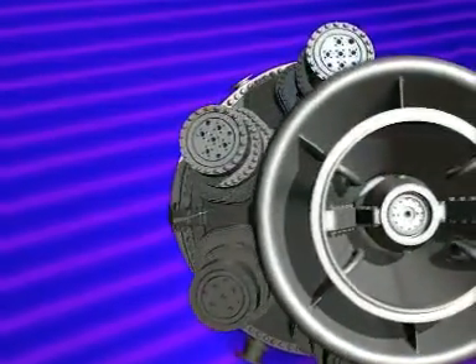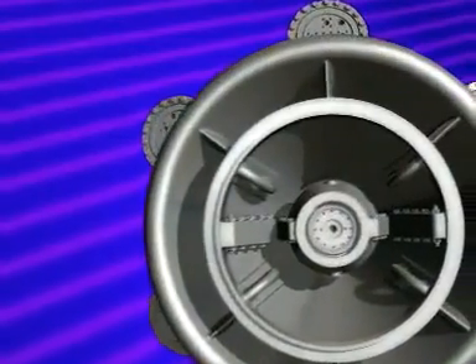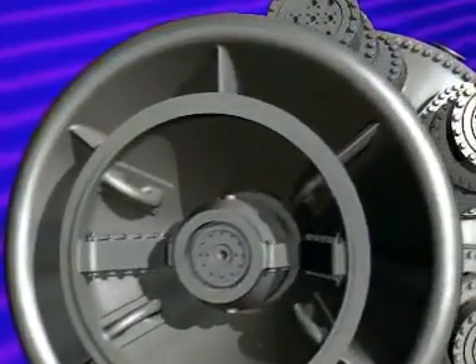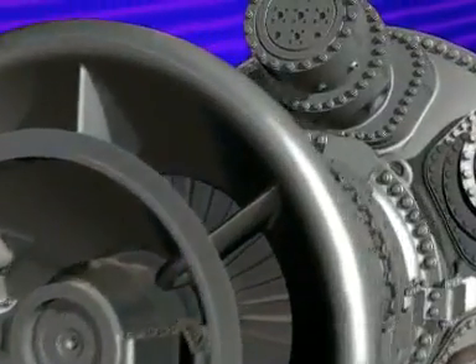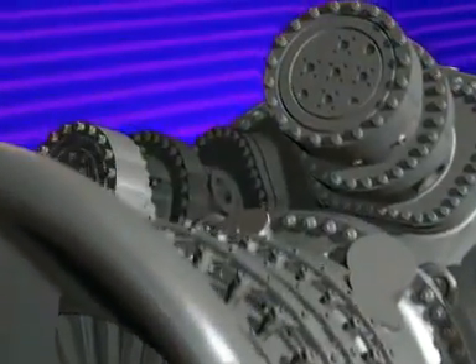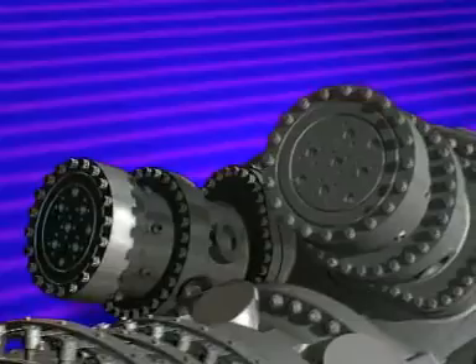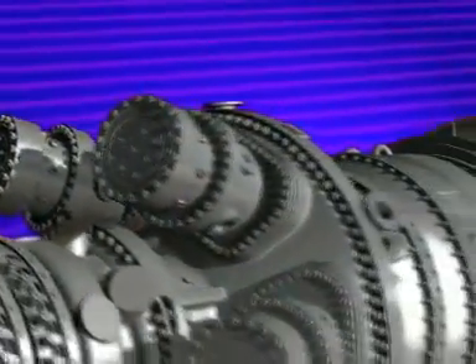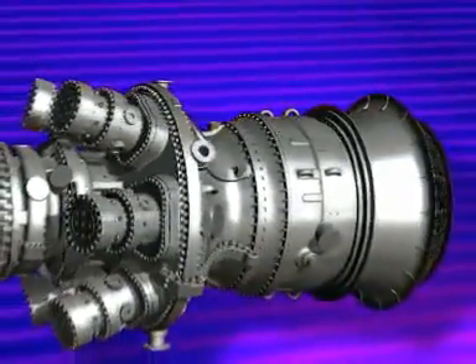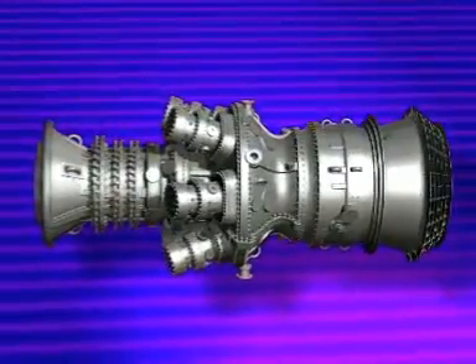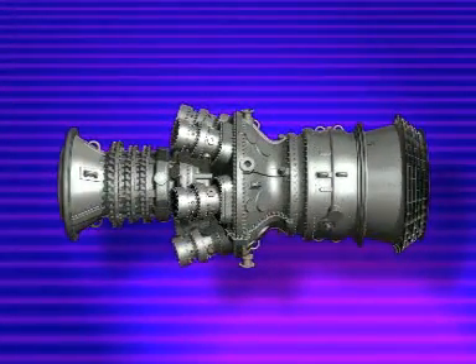Moderate firing temperature permits the achievement of high availability and reliability, and the use of a dry low emission combustion system derived from the GE Energy Dry Low NOx DLN2 guarantees the reduction of the NOx emission level to 25 ppm.